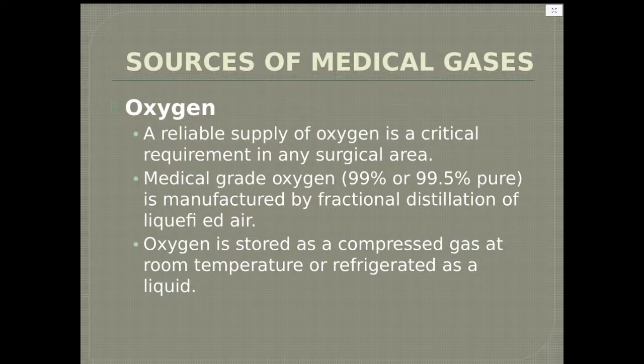And about oxygen, a reliable supply of oxygen is critical requirement in any surgical area. Medical grade oxygen, 99% or 99.5% pure, is manufactured by fractional distillation of liquid air. Oxygen is stored as a compressed gas at room temperature or refrigerated as a liquid.